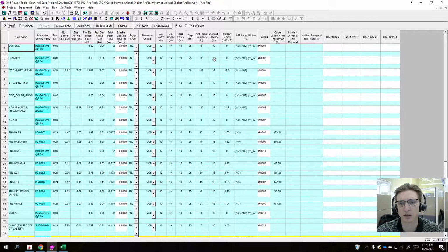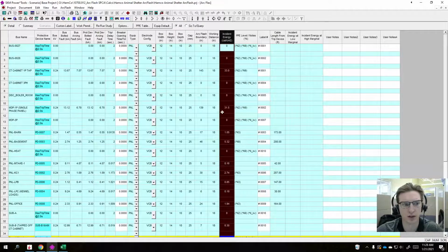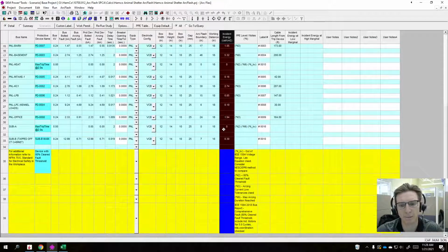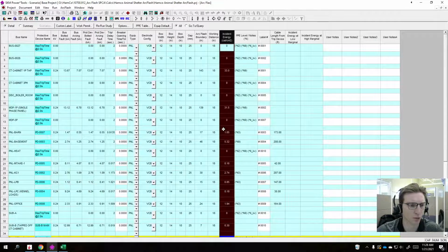Apparently, nominal voltage on some of my cables hasn't been set, so I'll have to take a look at that. But now you're going to get this report here, and we can see our incident energy is in this column right here. It looks like it actually ran it for both of my single lines right now. I think both of them are open, and that's why one of my single lines isn't finished, that's why I got that error.